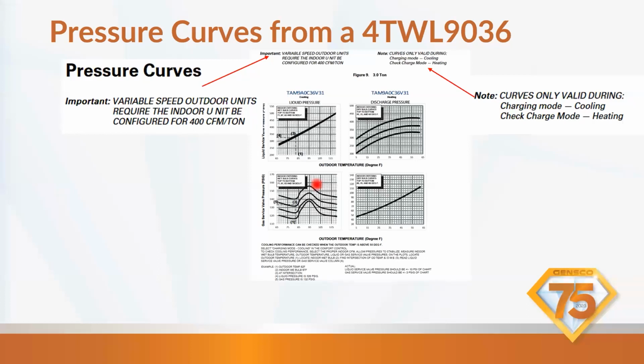And again, important, variable speed outdoor units require the indoor unit to be configured at 400 CFM per ton. This is out of a side discharge variable speed. And it states in there, again, it has to be at 400 CFM per ton because that's going to affect our charge. I like to put this in here too, that in the variable speeds communicating, we have to be in charging mode cooling or check charge mode heating. We have to be.